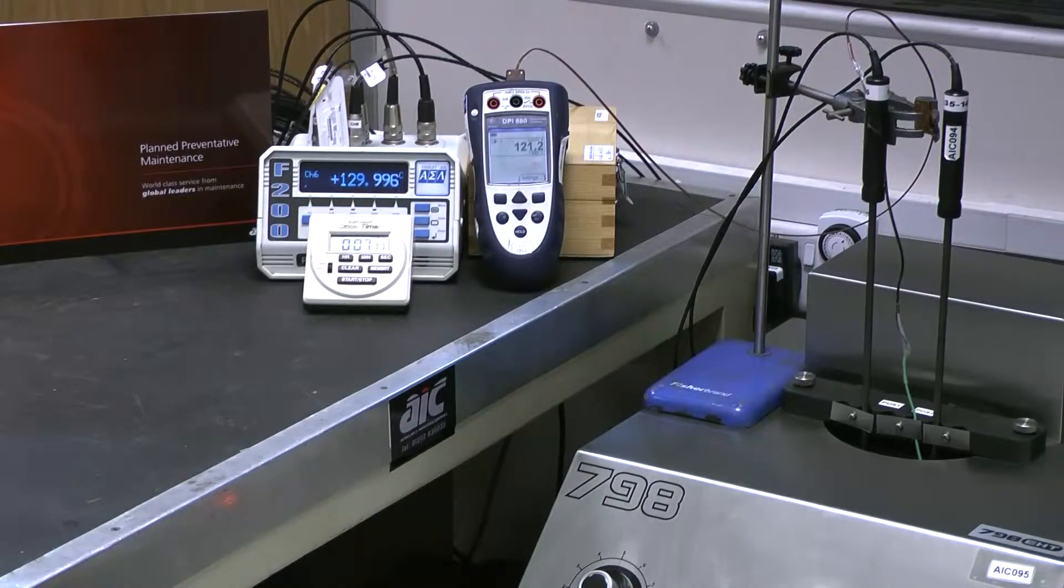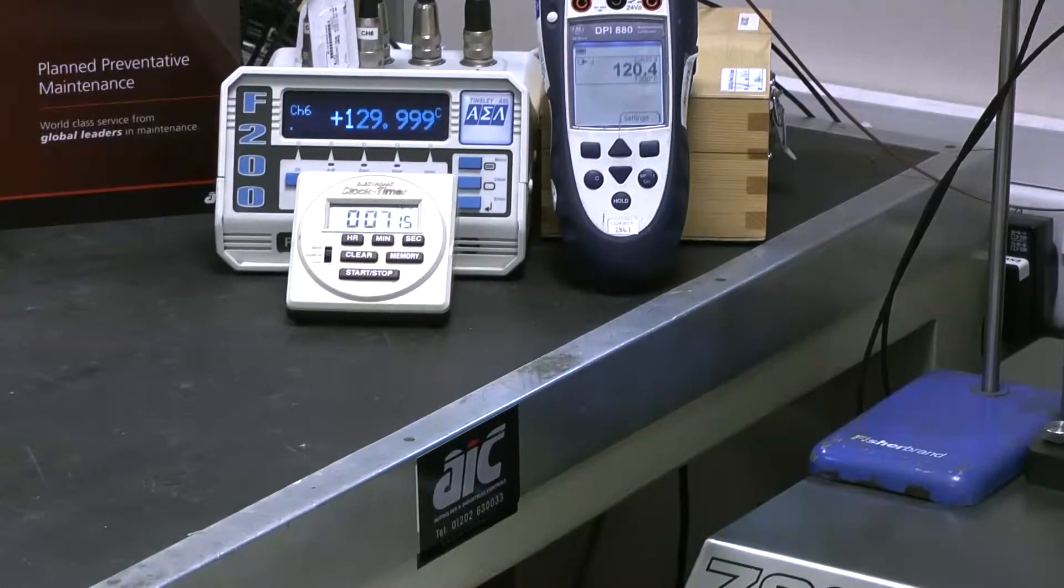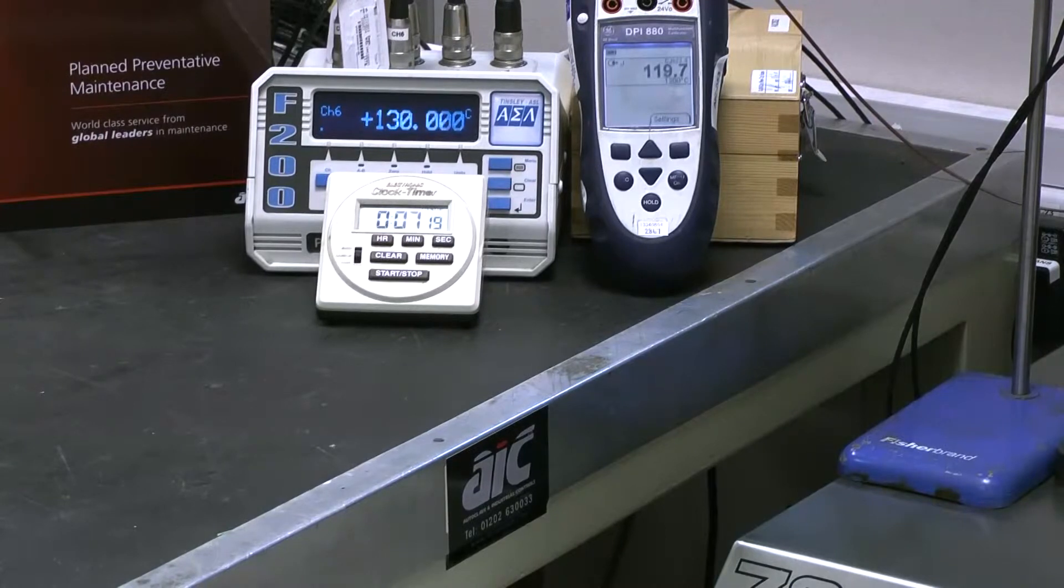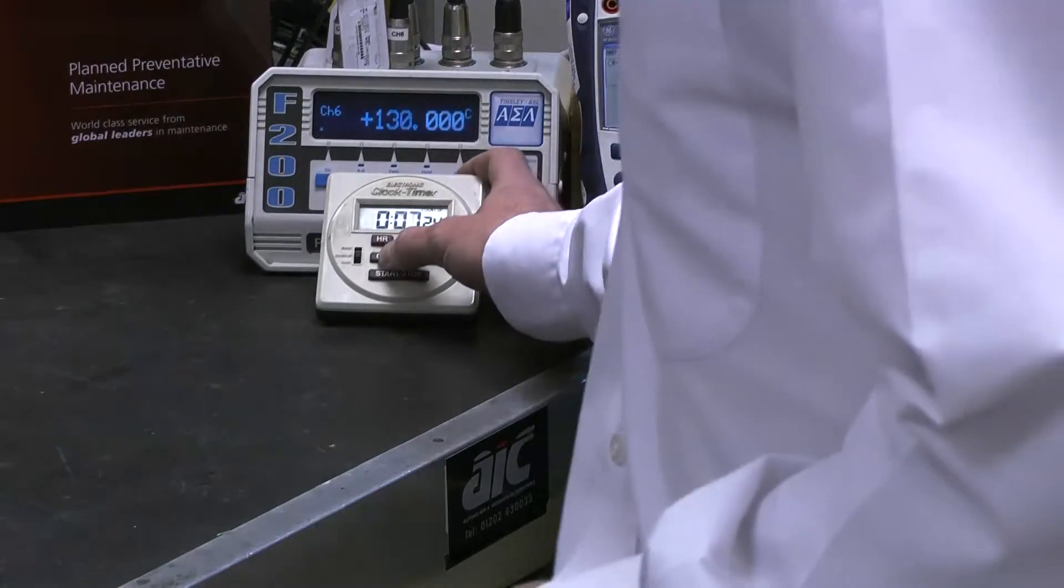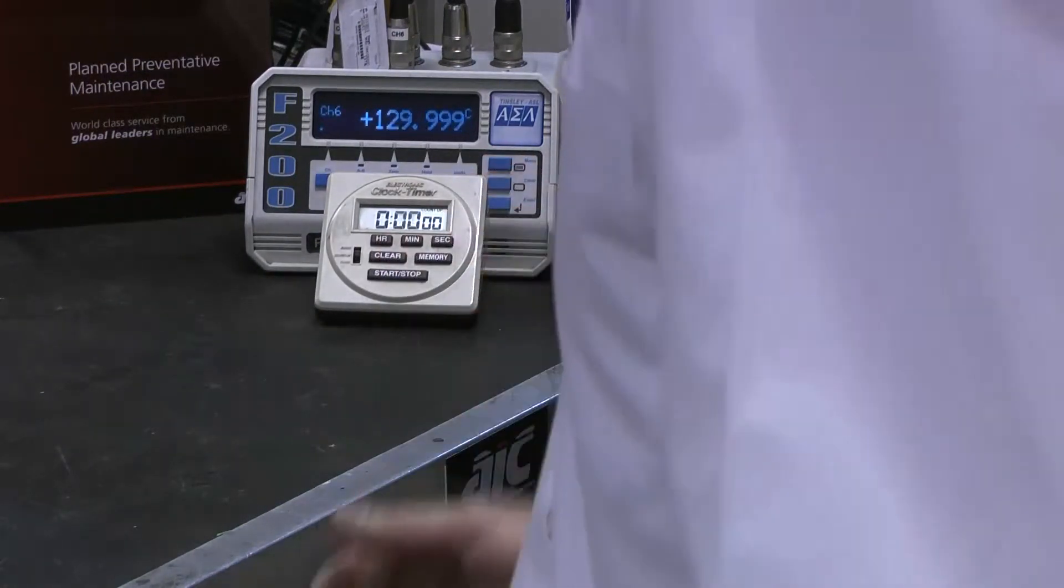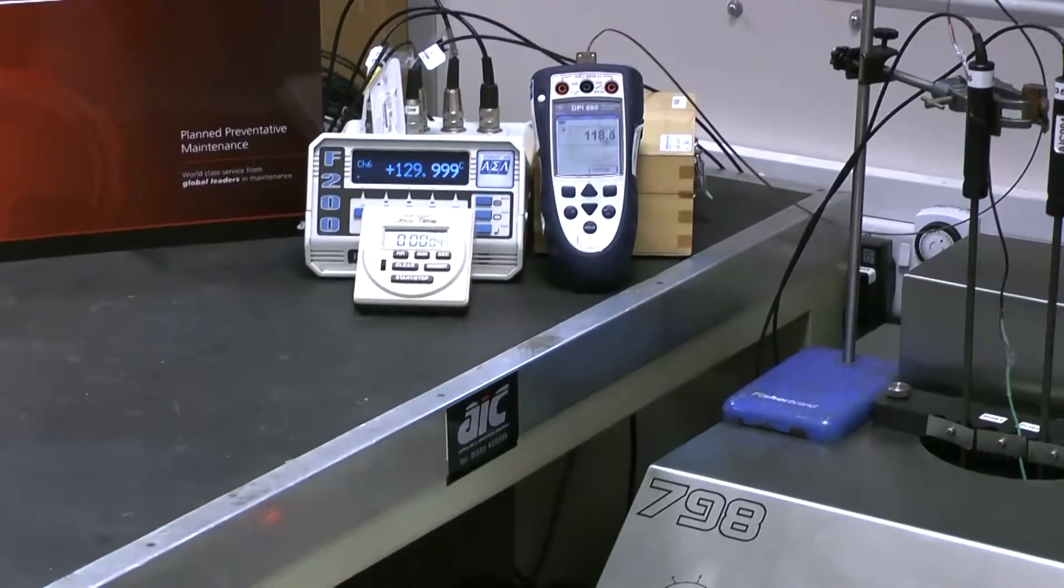And already the reading on our process calibrator is starting to go into error. So what I do, I'm just going to clear and restart the timer and get another five minutes to stabilize at this temperature. So, without fiddling with the wire there.